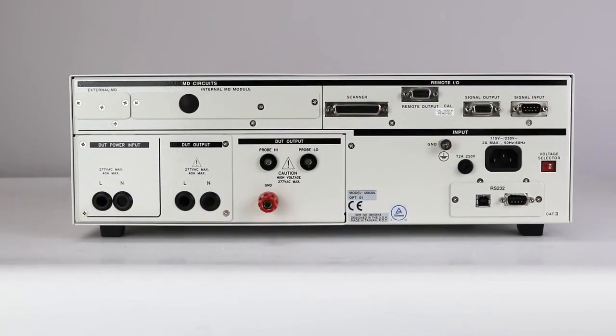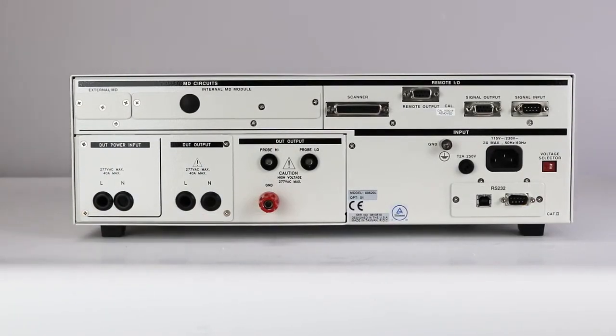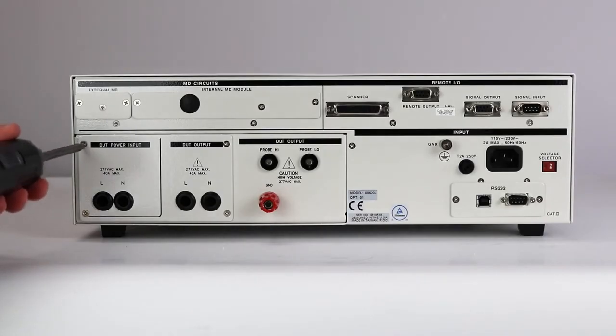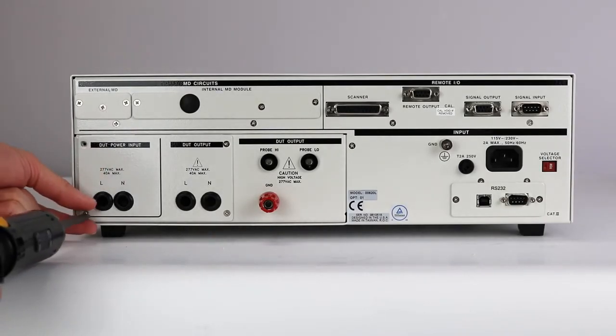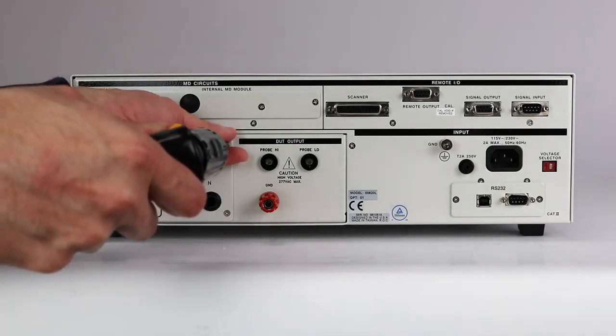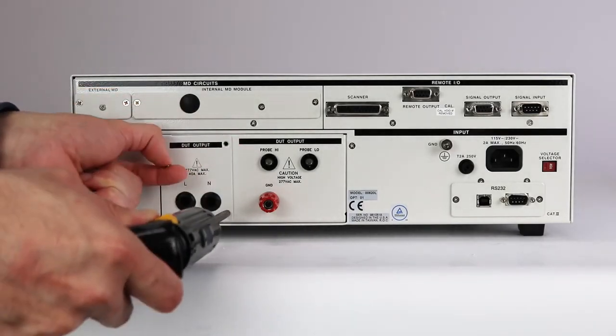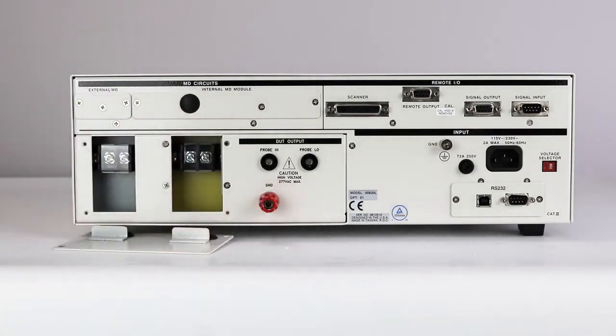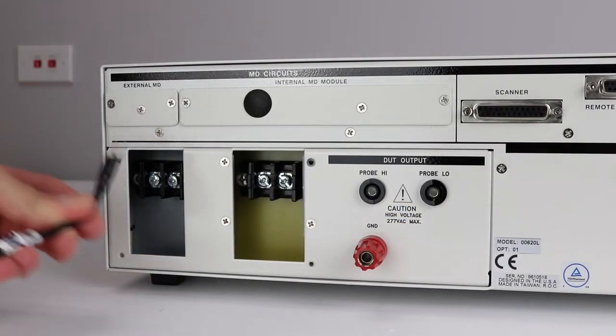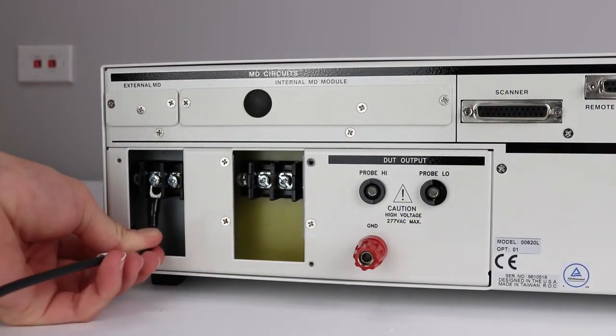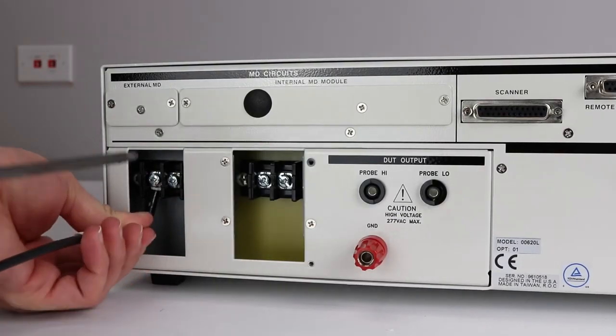First, we need to connect an external power source for our line leakage tests. Remove the cover plate on the rear panel of the LINECHEK to access the DUT power input connections. These terminals provide the connections for an external power source to the LINECHEK. Use the 2-probe line cord to connect to an unbalanced single-phase power source.